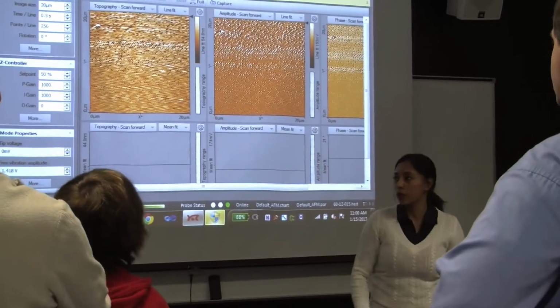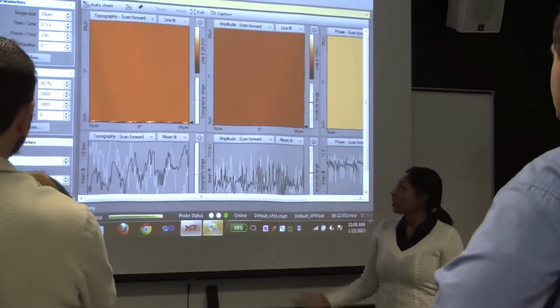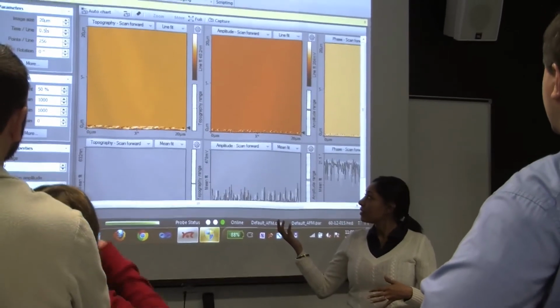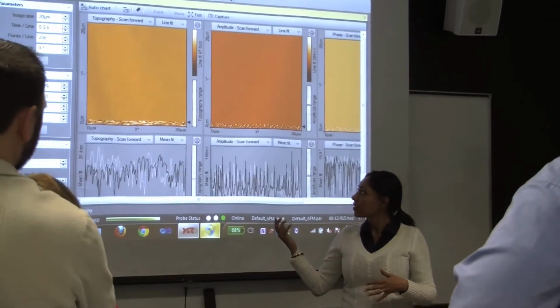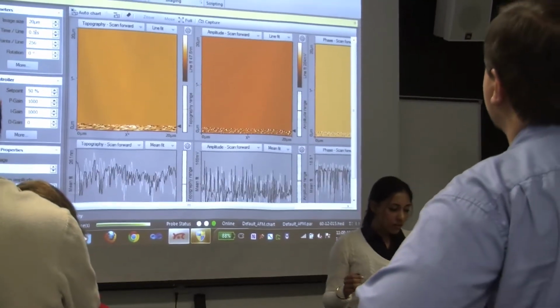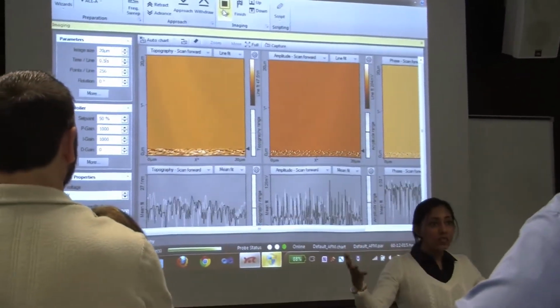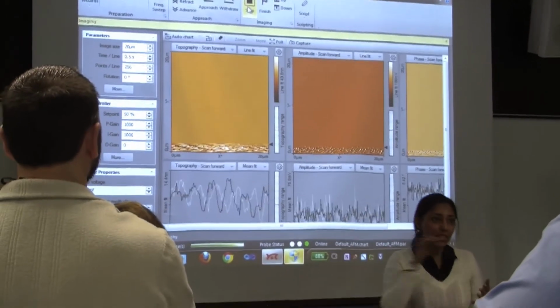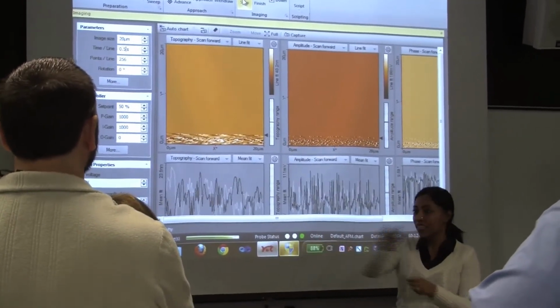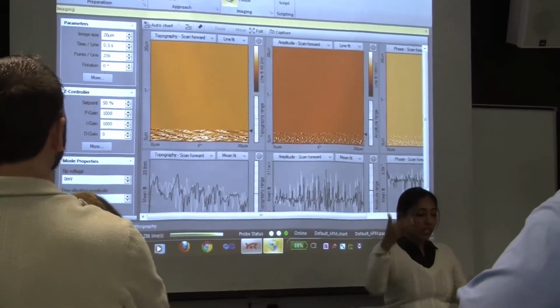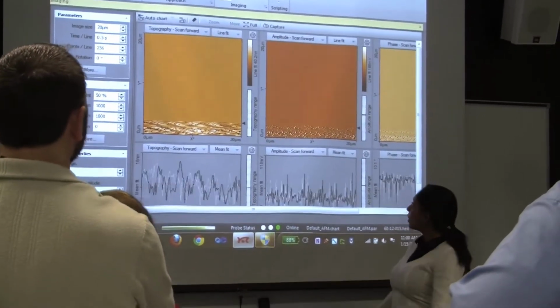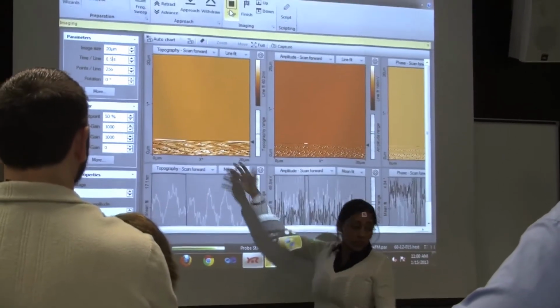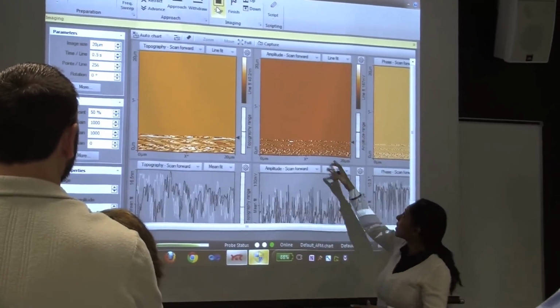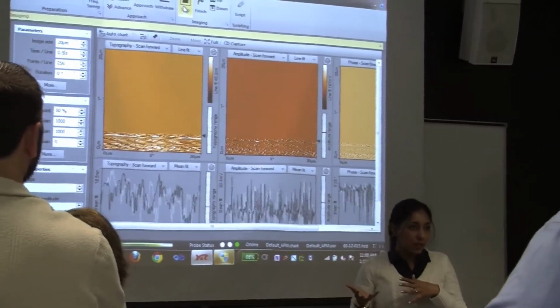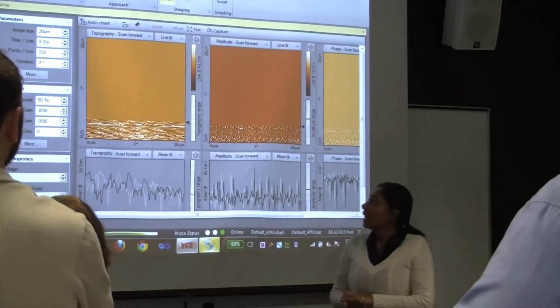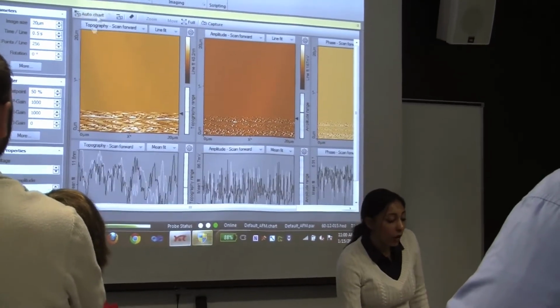I will explain all the parameters that we have. So right now, it's scanning line by line. You see how it is creating the picture. It's kind of exactly like how the TV creates a picture, like scanning it. It's slower, of course, but that's what it's doing. You have this little scan cantilever moving across your sample, scanning line by line, forming an image right in front of you. This is the topography, the surface topography. This right here is the amplitude scan of the tip, the vibration amplitude.